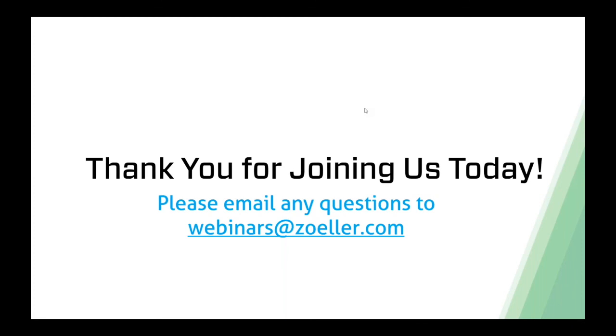There was a question about control panels. If you're using a Zoeller pump, must you use a Zoeller control panel? It kind of depends on the pump that you're dealing with. The answer is no, you don't have to use a Zoeller control panel. For the more sophisticated pumps that we offer, when you get up into some of our more expensive line, we would encourage you to use ours because we have features in our control panel that make use of features in the pump. But generally speaking, control panels, depending upon the application, can often have a very simple function, and you would not necessarily have to use ours.